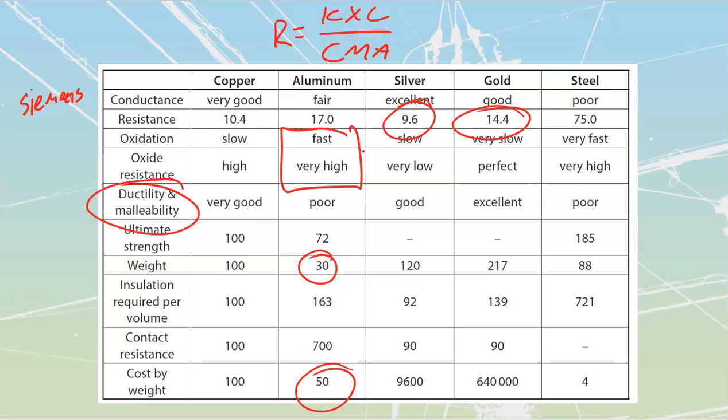You cannot just put anything onto those splices. They do need to have something on it. If you don't place anything onto those splices, they will oxidize, and that oxidization is going to be a high value of resistance, which is like having a series resistor in line with that. Usually what you should be doing is brushing them, not with a really stiff brush, but with a light brush. You're going to brush off any oxidization because it is soft, and then you are going to apply the penetrox onto them. Make sure they're fully coated.